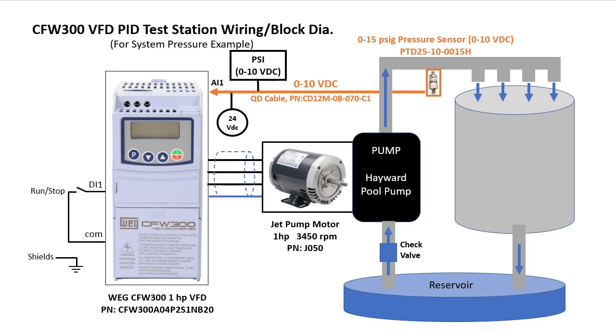We'll control run stop with a switch on digital input 1 and we'll use digital input 2 so we can switch between controlling the drive output automatically by PID or manually by us.